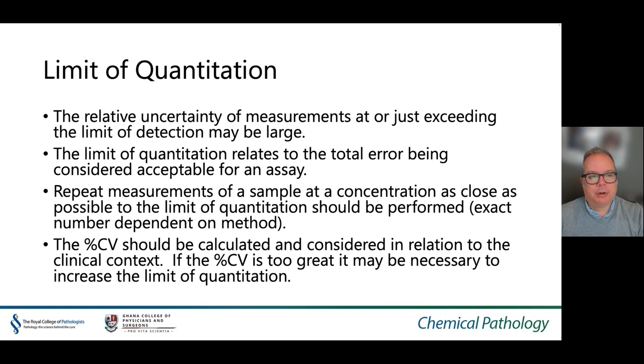The limit of quantitation relates to the total error being acceptable for the assay. The relative uncertainty of measurements at or just exceeding the limit of detection may be large. To obtain this, repeat measurements of a sample at a concentration as close as possible to the limit of quantitation should be performed — a minimum of 10 replicates should be considered. The percent CV should be calculated and considered in relation to the clinical context, i.e. the target specification set at the beginning of the exercise. If the percent CV is too great, it may be necessary to increase the limit of quantitation until the CV meets the required target.